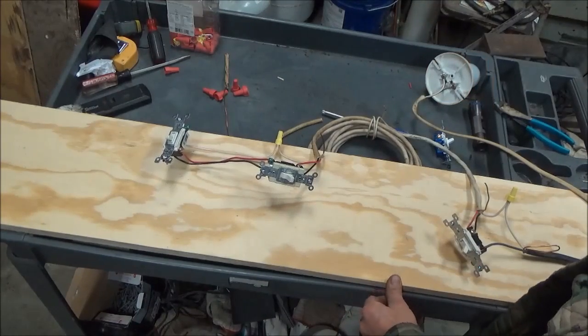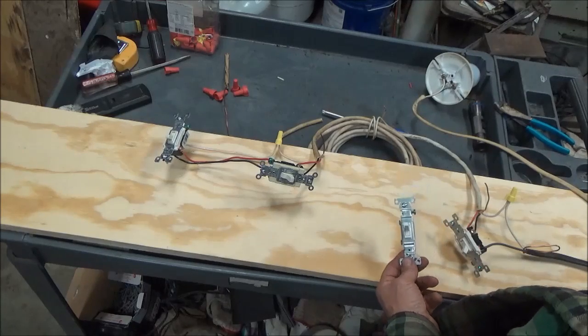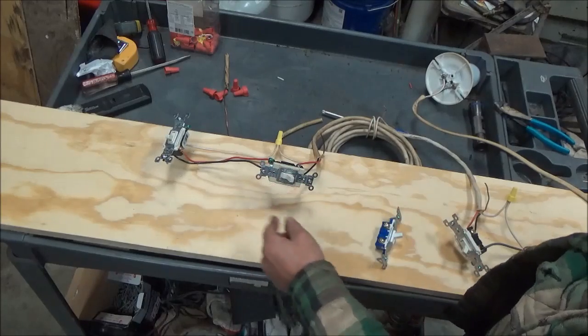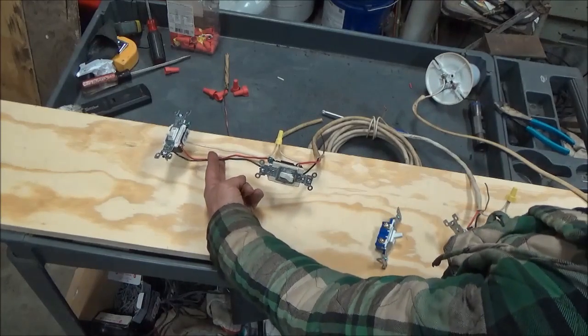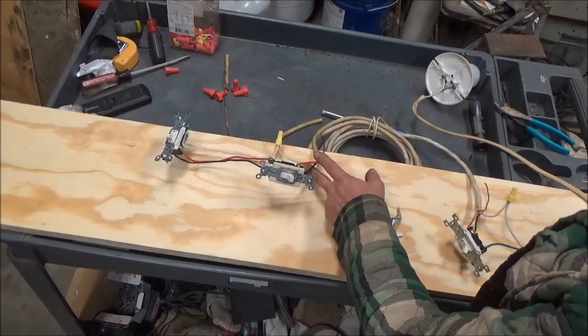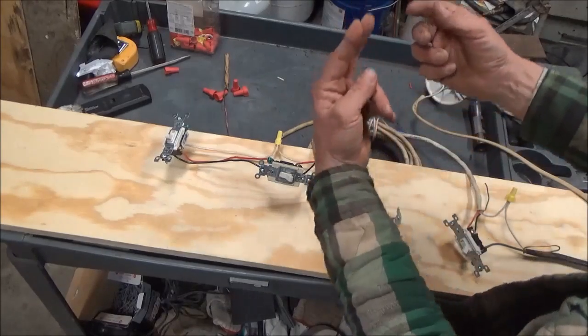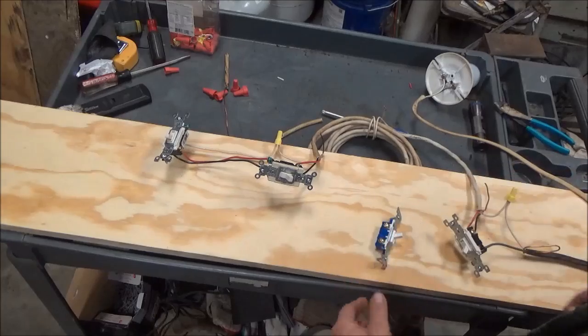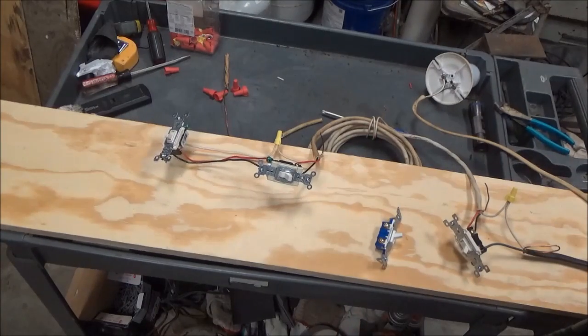So, there's your simple, basic circuit for your three-ways. And I added all that in from where a standard single pole that you have in your doorway when you walk in a room that only has one switch. That's the switch you have. So, you can just take that switch out and put a three-way in and add. And if you want to put six or eight or ten switches, all you need is more four-ways all along these travelers. Anywhere you have to have a three-way at the beginning, and you have to have a three-way at the end. And anywhere along the way, you can cut that wire, put a junction box there, and then add two pieces of Romex, two pieces of 12-2 with ground, coming down into your switch box. Anywhere you want to do that, you can just tap into this wire, cut it in half, put it together, and you'll have another switch. I hope that helps somebody. Thank you for watching.